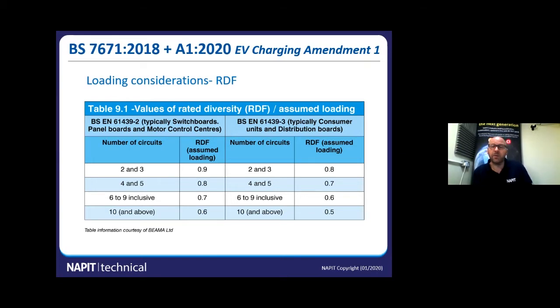So we've got an issue there, because most of these cars have a 7.4 kilowatt inverter in them, so they'll be looking for a 32 amp charge. If we've got a 32 amp continuously loaded circuit breaker, and we were to apply this factor, we would need to double the circuit breaker for it to work correctly, because circuit breakers, as you know, have a bimetallic strip in there. It works on temperature, and when it gets to a certain temperature, it feels there's an overload, it switches off. If the heat can't escape because of this constant loading, the circuit breaker may not hold the charge. So taking this loading factor into consideration, we would need to put in double the circuit breaker, but they don't do a 64 amp. We'd have to have a 63 amp circuit breaker in there, and of course that causes a problem because we would now need larger conductors in our circuit.